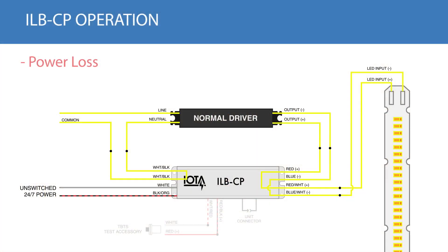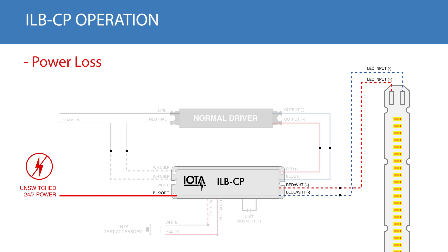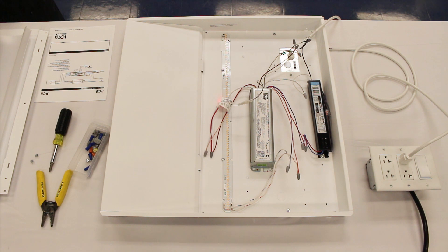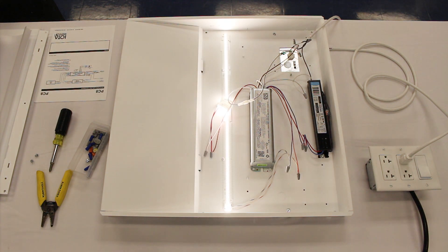During a power loss, the ILB-CP will detect the loss in power through its black-orange normal power sense, and switch to powering the LED module from its internal battery, ignoring any control devices that interface with the normal LED driver. This ensures that your LED lights are illuminated during a power loss situation regardless of wall switch position.